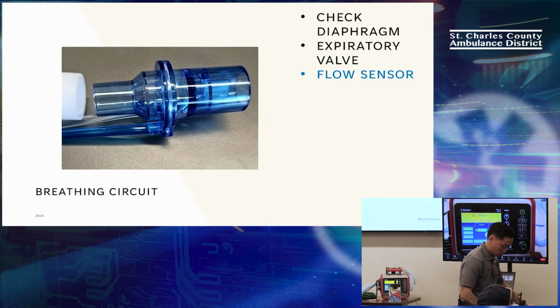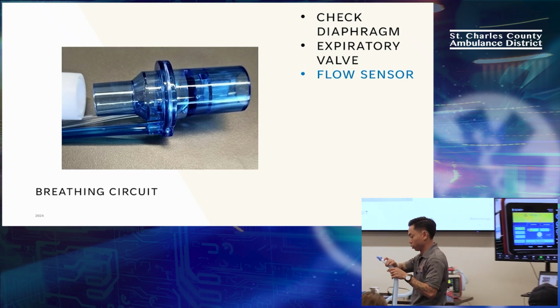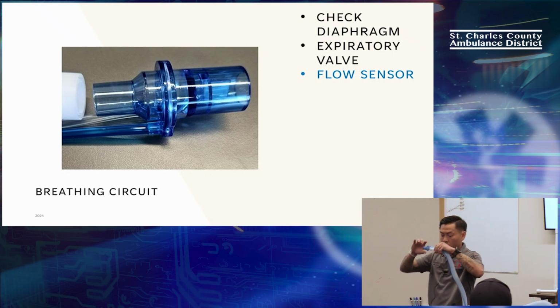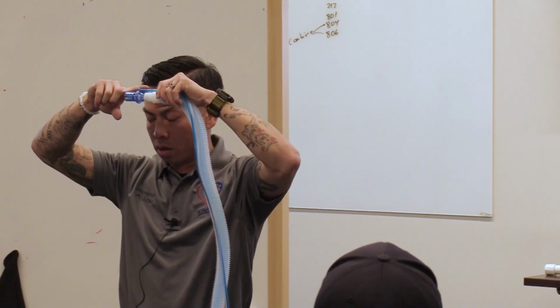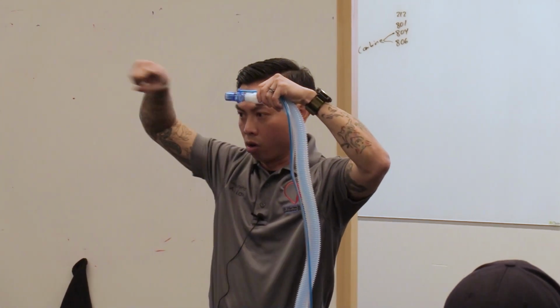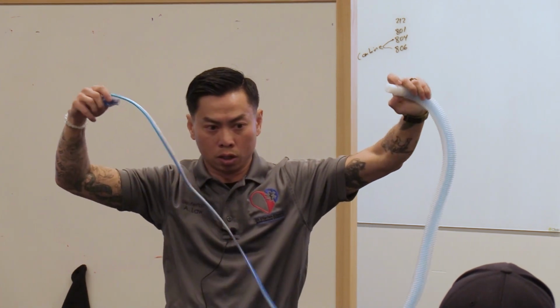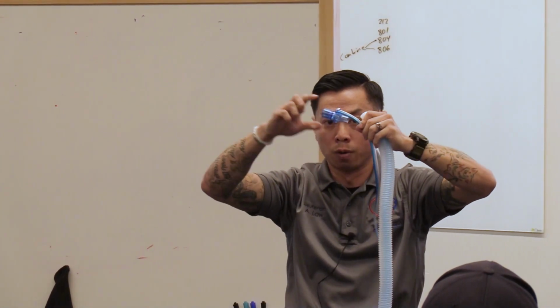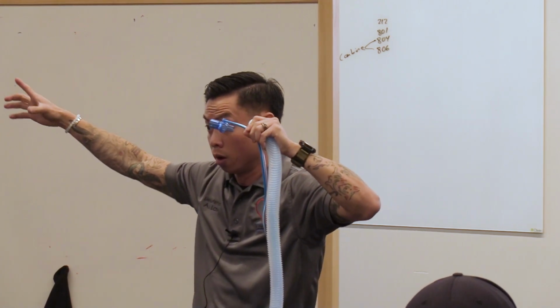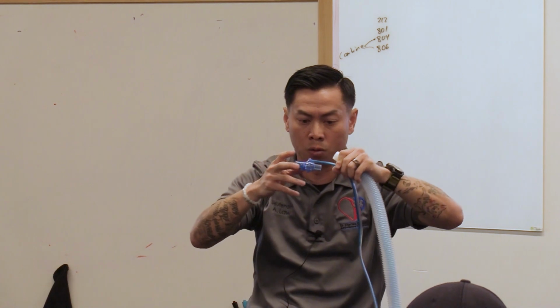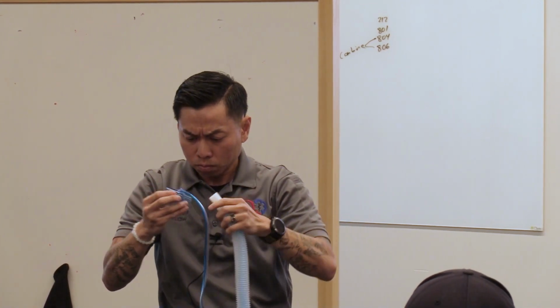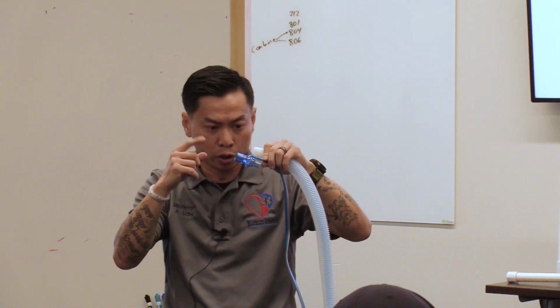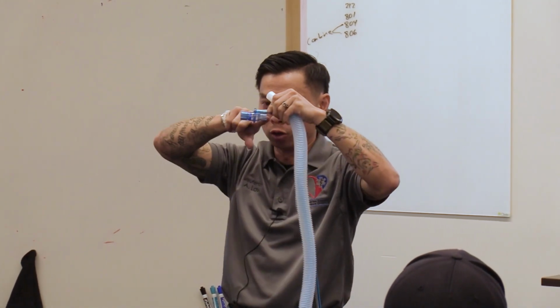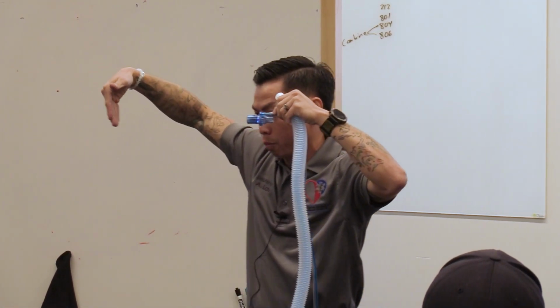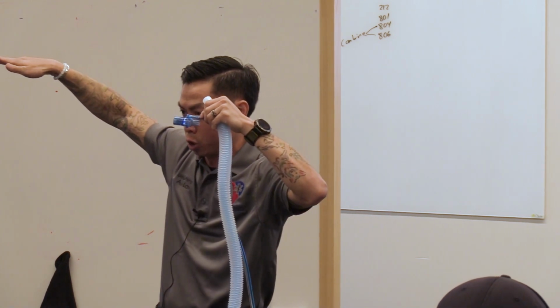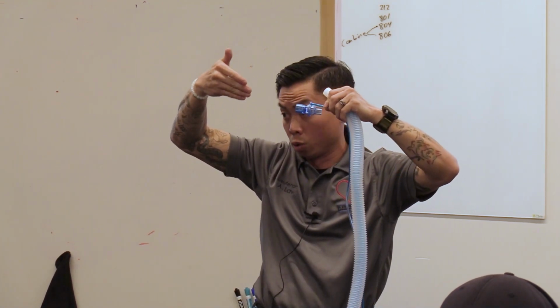All right, so next, this is the other half of the magic, the flow sensor, right? The cool thing about this is it measures the milliliters from this side on. So we can add neb treatments, everything else in between, but when we say 500 mils, it's measuring 500 mils from here onto the patient, so that we know the patient is getting the 500 mils short of the ET tube and everything else. If you look inside the flow sensor, you see a little clear plastic membrane, and it's like a chevron cut. So when air is going through on the inhalation, that trap door, the chevron membrane, goes away, right? And so when the patient exhales and air is coming back through the circuit, the chevron goes that way.